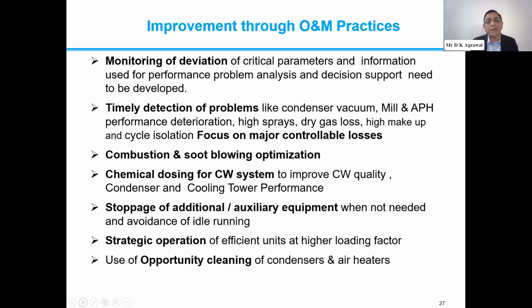Similarly, as I told regarding the chemical cleaning, chemical dosing, it's very, very important. And if we are not taking care of this properly, there are going to be algae deposits in the cooling tower. If the water is not of proper quality, then there are going to be hard deposits, which sometimes become difficult to remove in the condenser tubes.